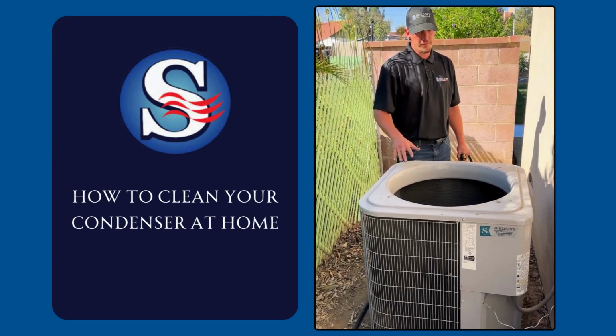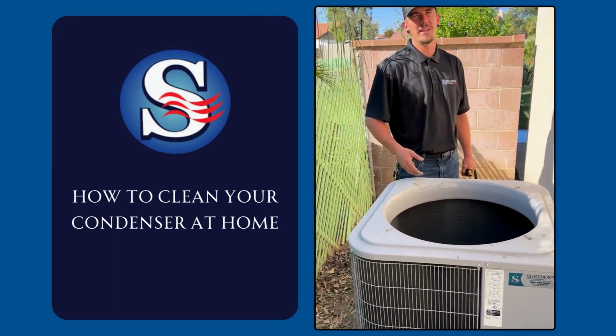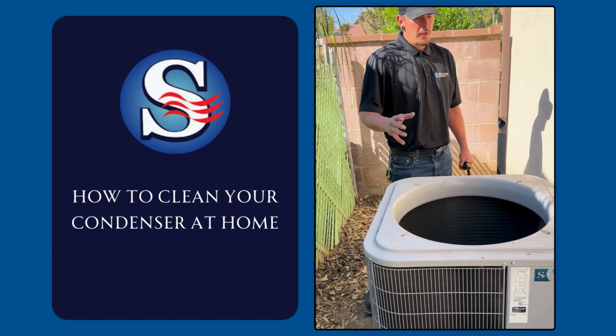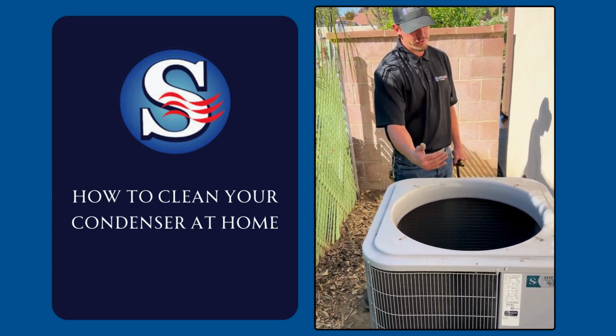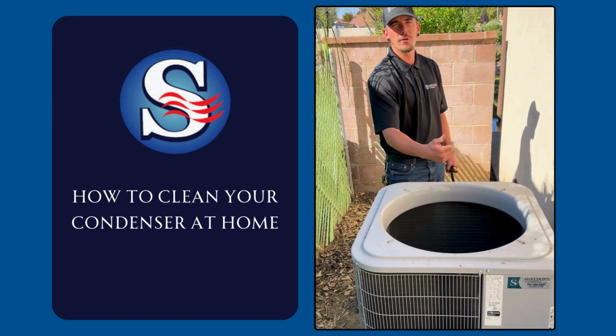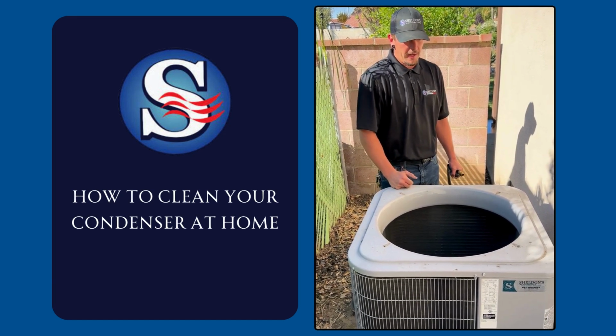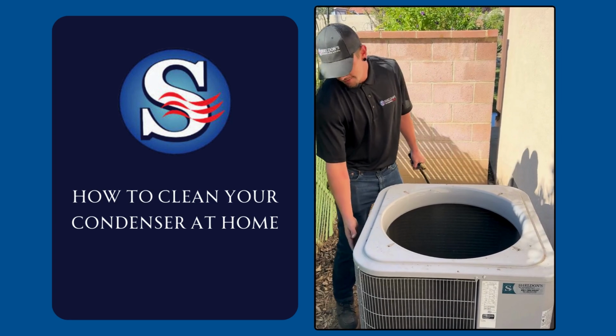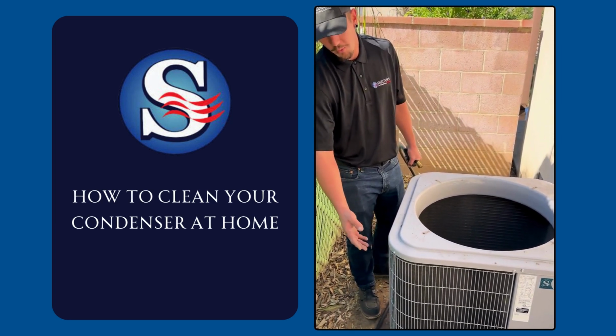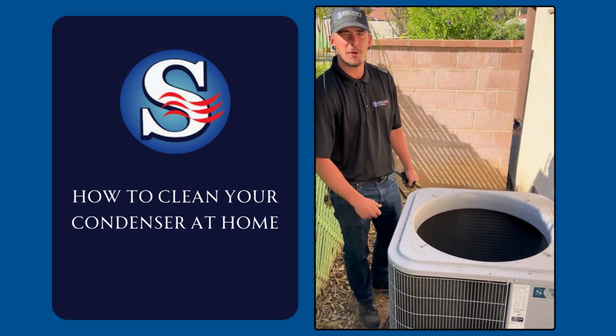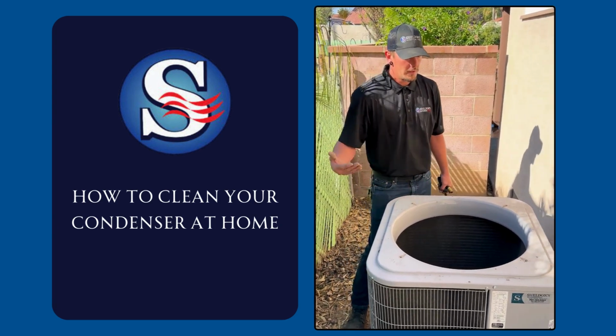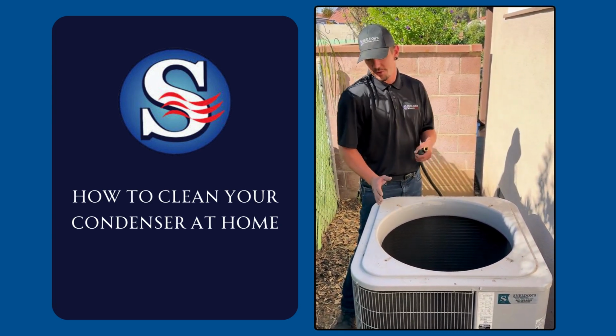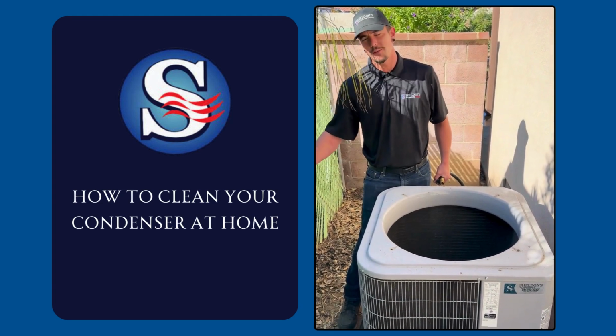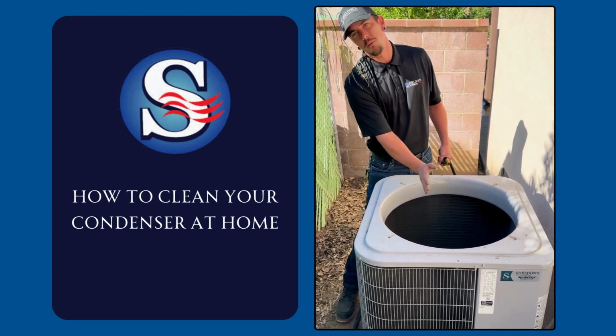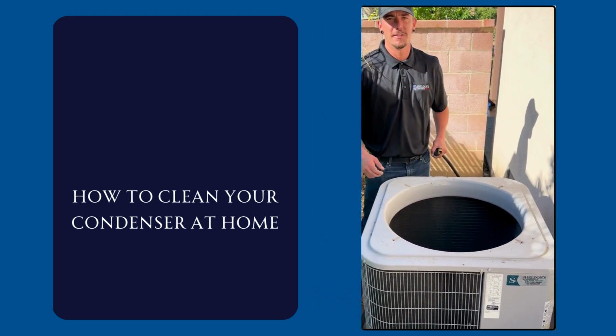So these coils are very delicate, so you don't want to clean them with a pressure washer. You want to hit the coils straight on. You don't want to hit them at an angle because you might bend the fins. When they have a light dusting on the outside, you can get away with just rinsing the outside of the coil. But typically you want to spray from the inside out to push any of the debris out of the coil. Since it's getting pulled in, you're going to want to push it out the opposite direction.